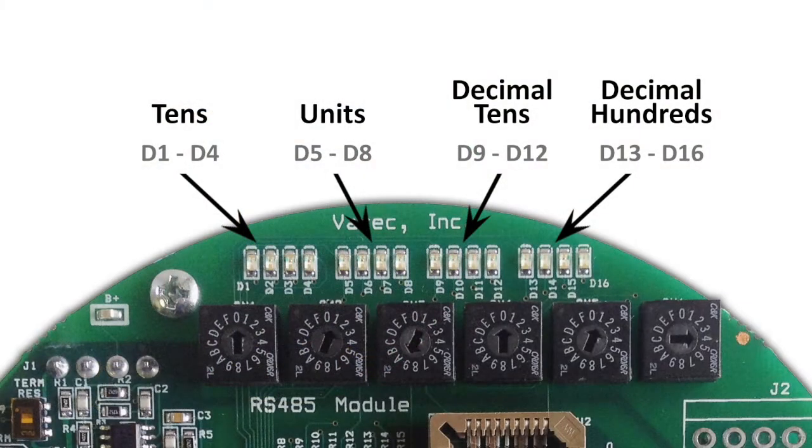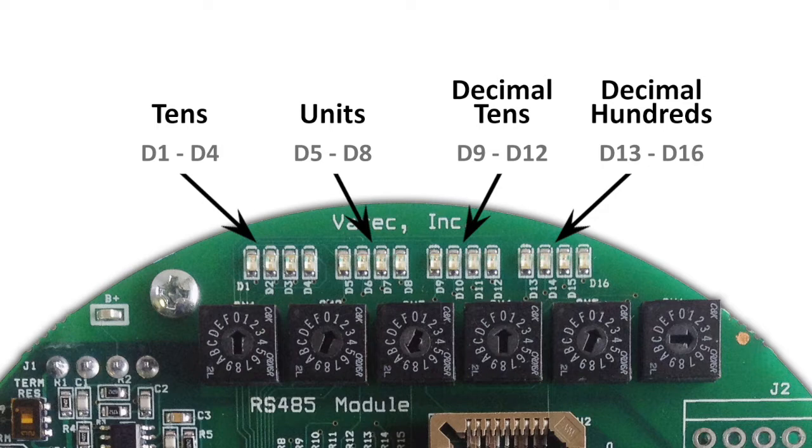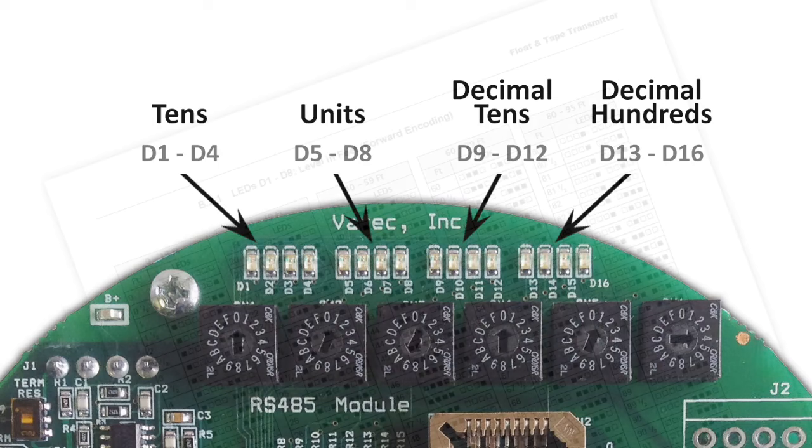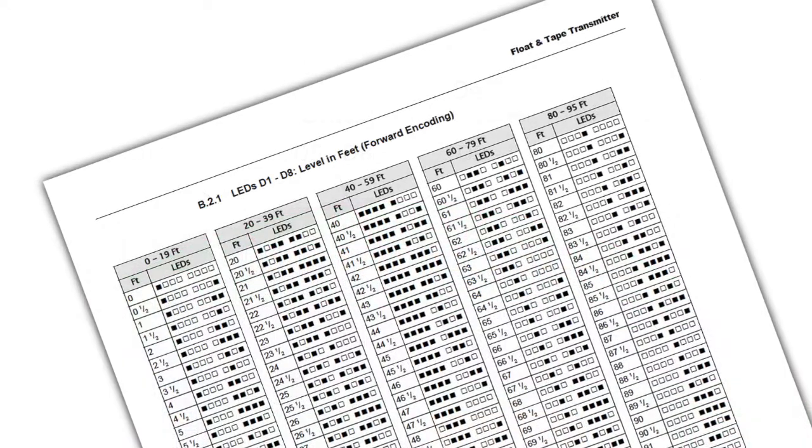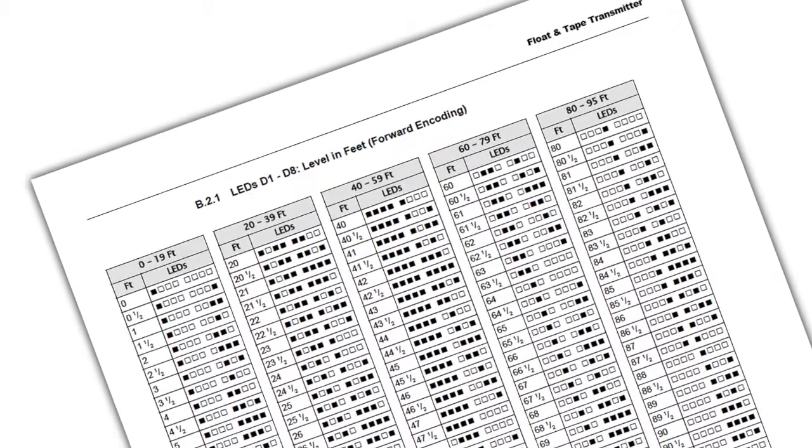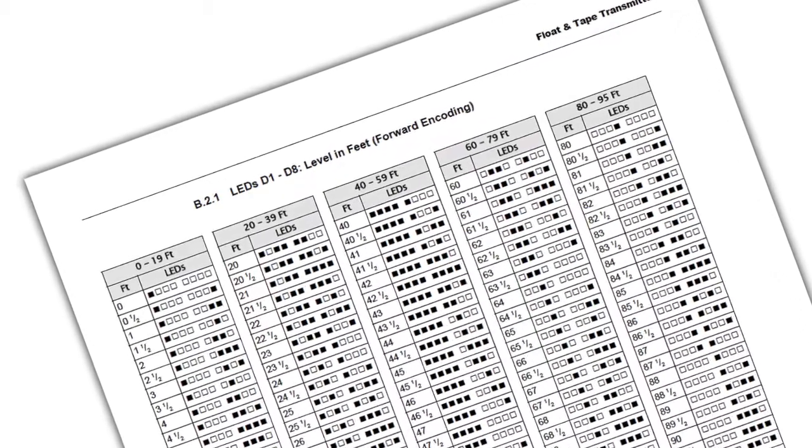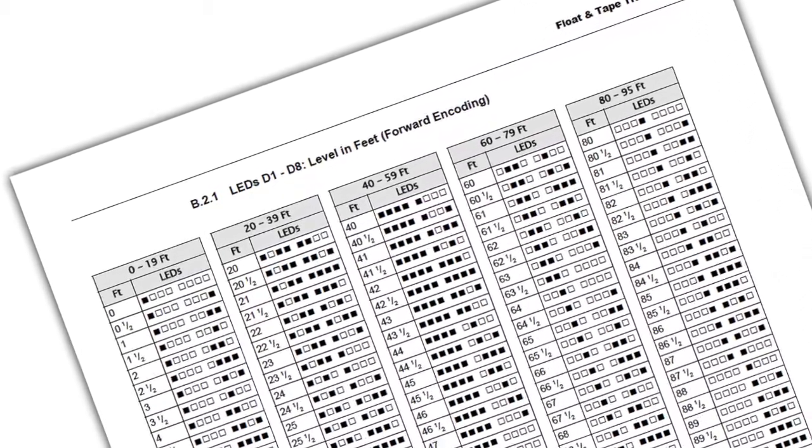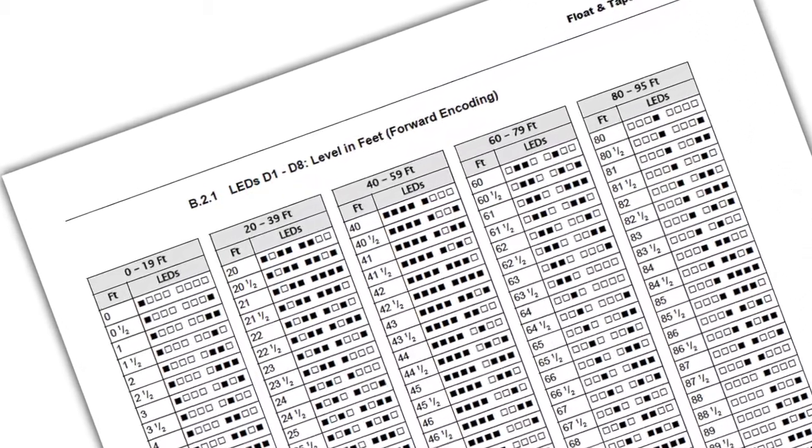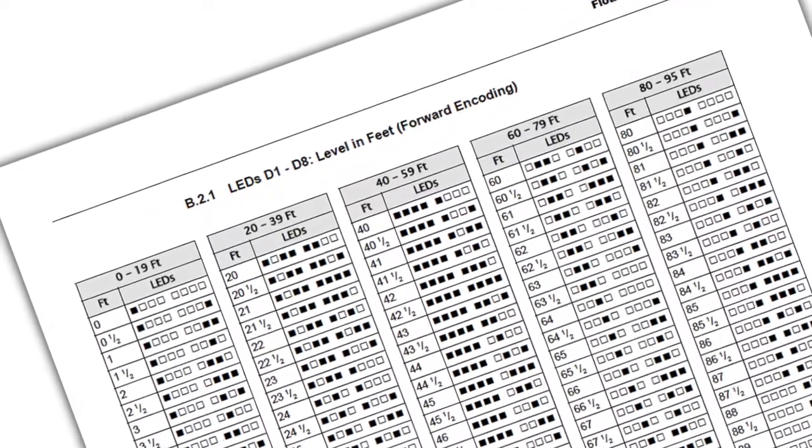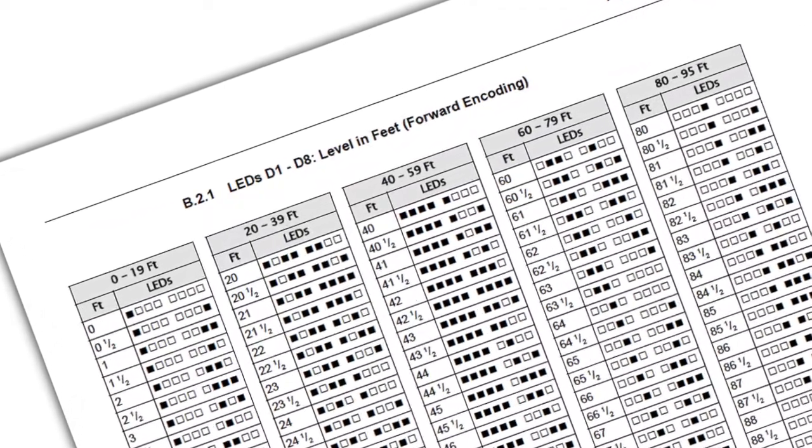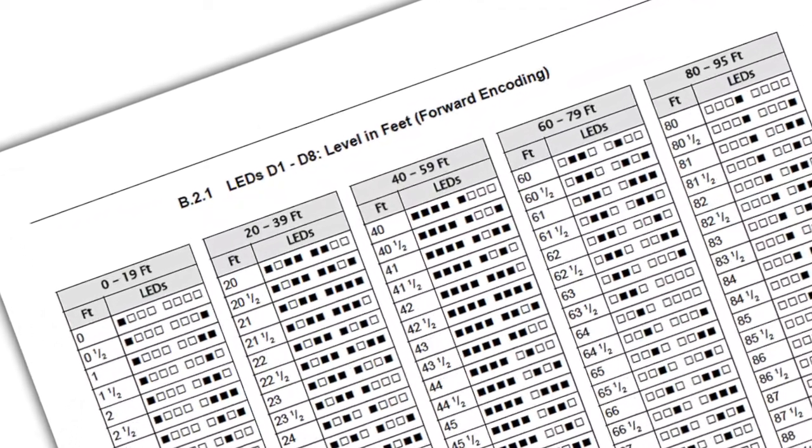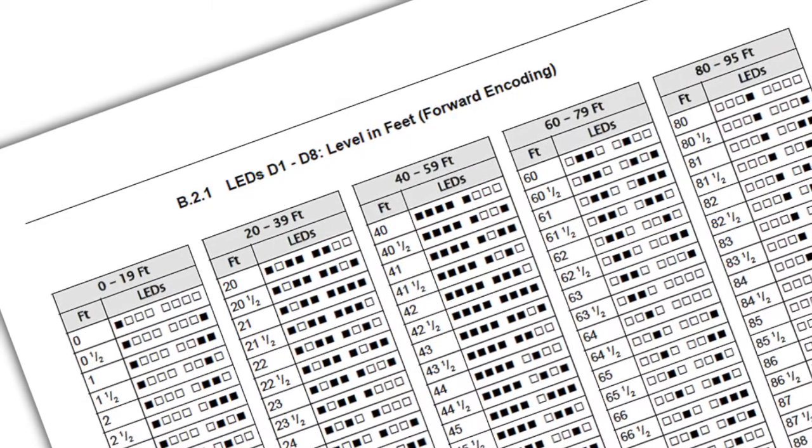The LEDs present the level in a binary format with D1 through D4 representing the tens digit, D5 through D8 representing the unit digit, D9 through D12 representing the decimal tens, and D13 through D16 representing the decimal one-hundreds value. The format can be English or metric, depending on the data format we set using the SW5 switch. The manual includes binary conversion tables for English and metric units, so find the LED combination that matches your level reading as a decimal unit.